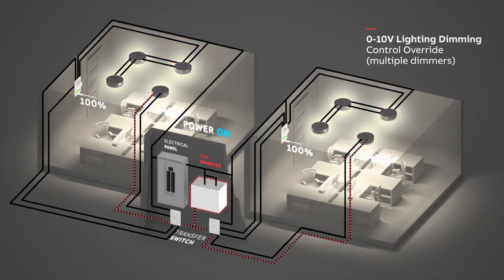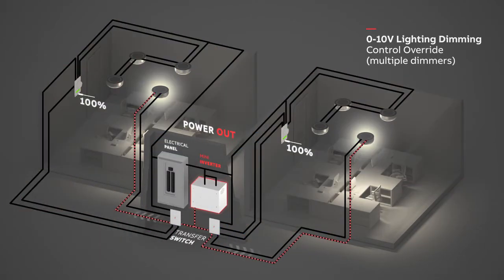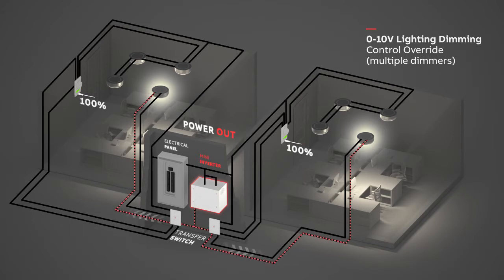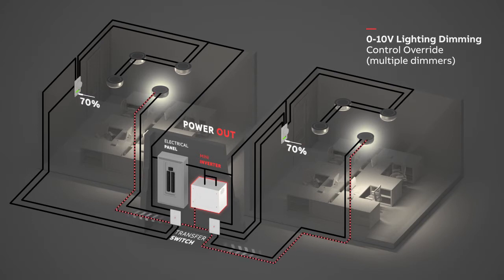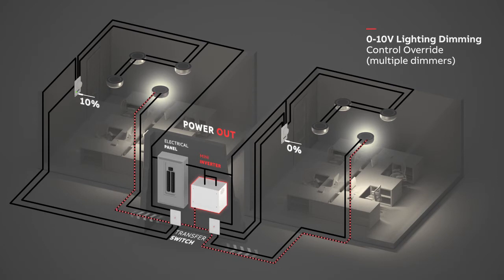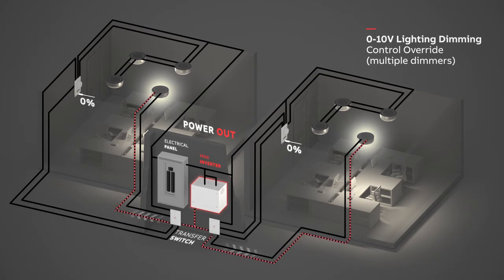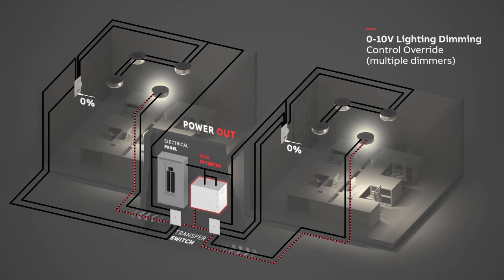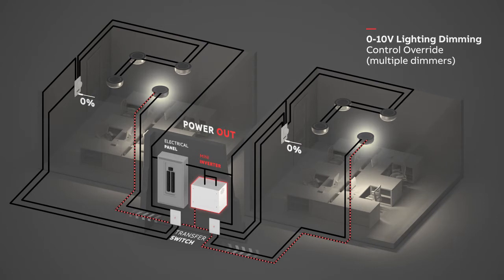When the main power goes out, the transfer switches will bypass the dimmers so that even if a dimmer is off or down, the lights wired as emergency lighting will turn on at full brightness, powered by the mini inverter.